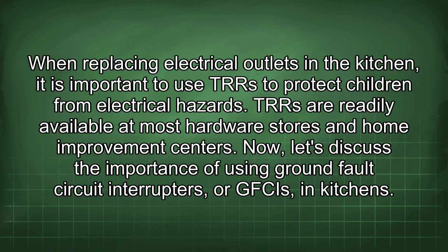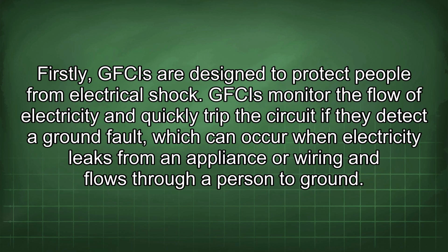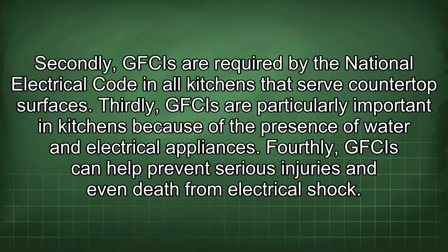Now let's discuss the importance of using ground fault circuit interrupters, or GFCIs, in kitchens. Firstly, GFCIs are designed to protect people from electrical shock. GFCIs monitor the flow of electricity and quickly trip the circuit if they detect a ground fault, which can occur when electricity leaks from an appliance or wiring and flows through a person to ground. Secondly, GFCIs are required by the National Electrical Code in all kitchens that serve countertop surfaces.